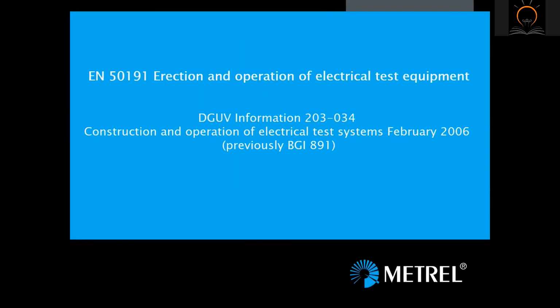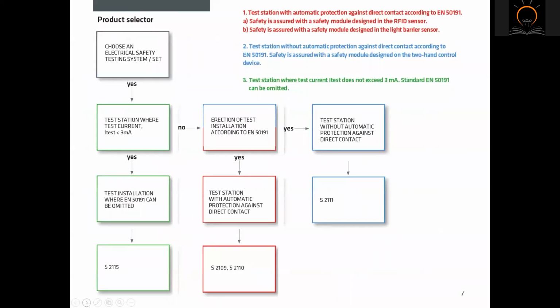The starting point for the design of the new product solutions is the European standard EN 50191. In Germany, it is recognized as DGUV Information 203034. According to the EN 50191 standard, there are a few options available for the execution of a test station, depending on the safety design. How to select the appropriate test station for your application? The answer lies in the flowchart.